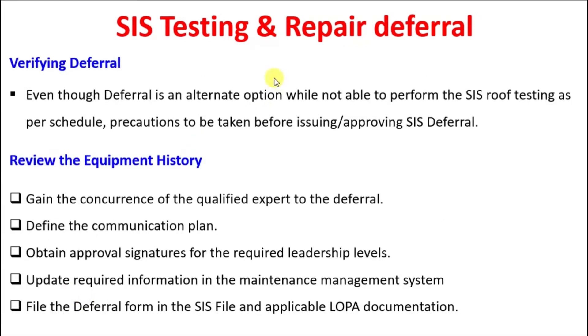Verifying deferral: even though deferral is an alternate option when SIS proof testing cannot be performed as per schedule, precautions must be taken before issuing and approving a deferral, reviewed and verified by multiple agencies. Steps include: review the equipment history; gain concurrence of a qualified expert; define the deferral and communication plan; obtain approval signatures for required leadership levels; update information in the maintenance management system; and file the deferral form in the SIS file and applicable documentation.